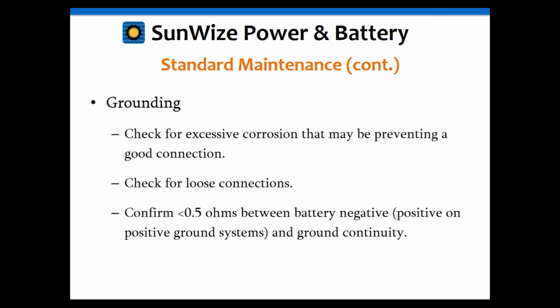To be honest, if your system takes a direct lightning strike, there's not much you can do. But if you have a nearby strike, it can induce a voltage on a wire. Matter of fact, any wire that is outside of your battery box that's more than 5 feet can have a voltage induced on it by lightning that's a mile or 2 miles away. By giving that voltage a path to ground, it helps that.